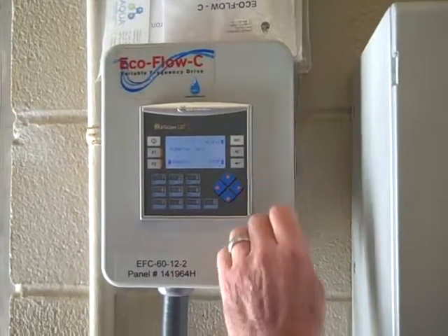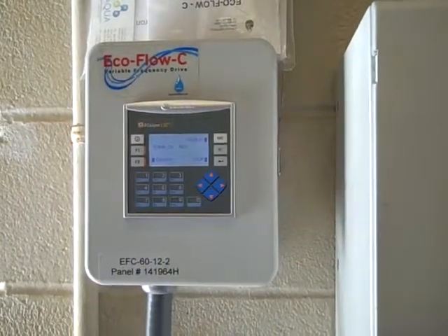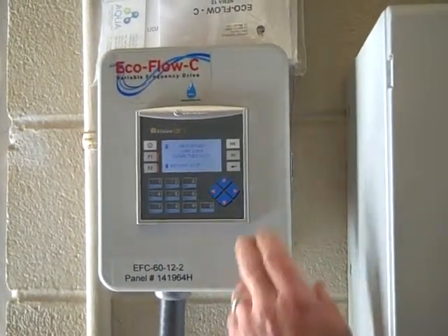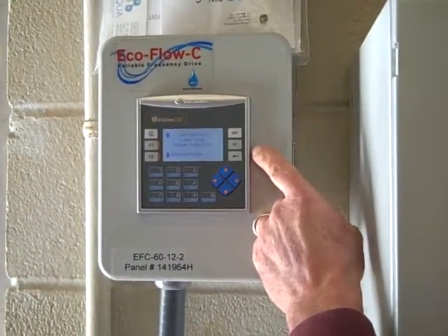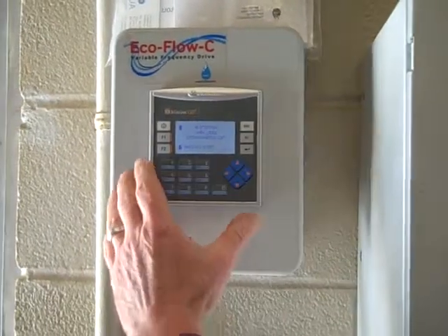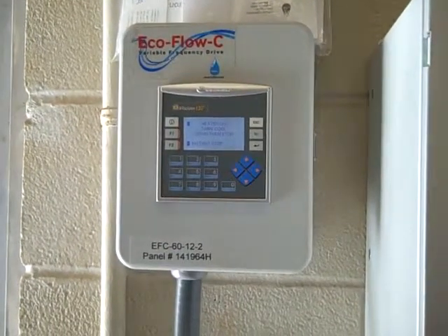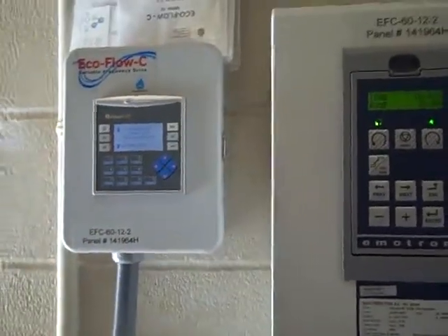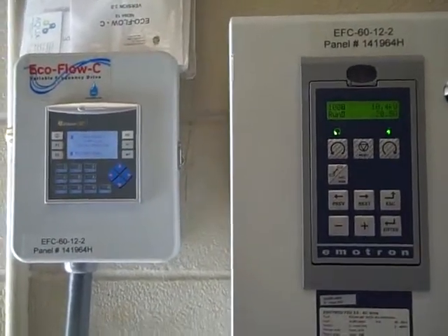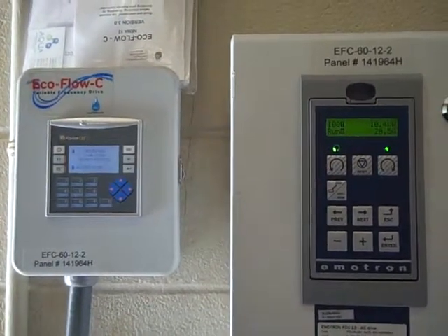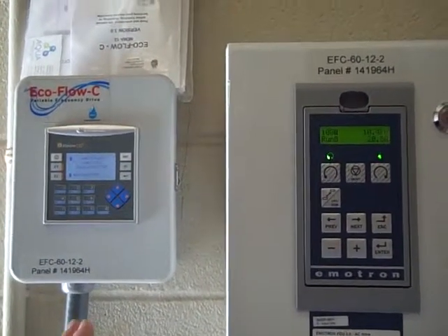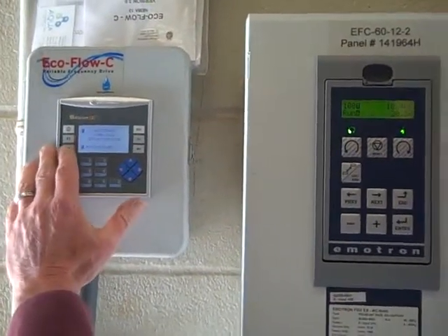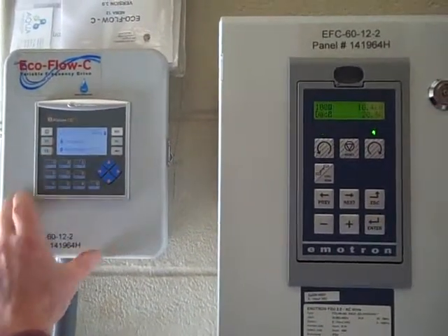Operations, fairly simple. You turn the pump off to backwash and turn it back on. There's your stop button. You have a heater UV 3-minute cool down. All that'll do if we hit that button right there is it'll let the pump run for another 3 minutes. That allows your heater to cool down. If you have a gas heater or a UV light, turns off, you've got to allow that to cool down also. So it just times it out for a 3-minute shutdown. That's not involved in yours, so we can do an instant stop.